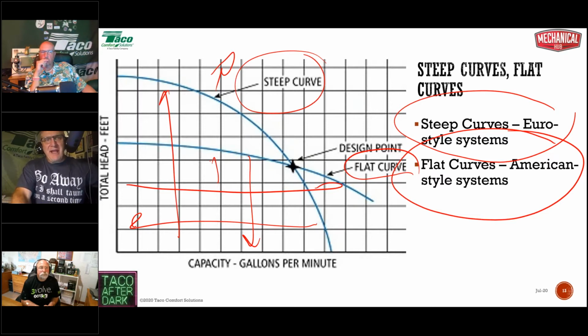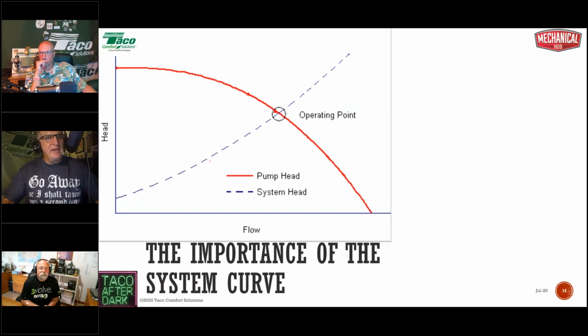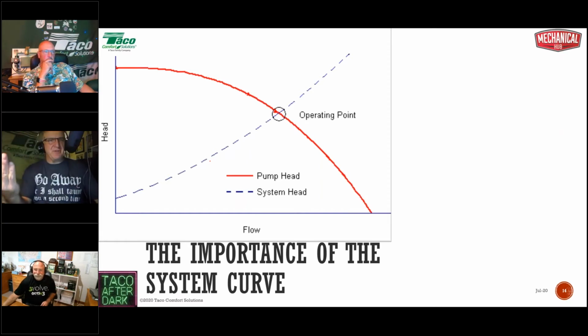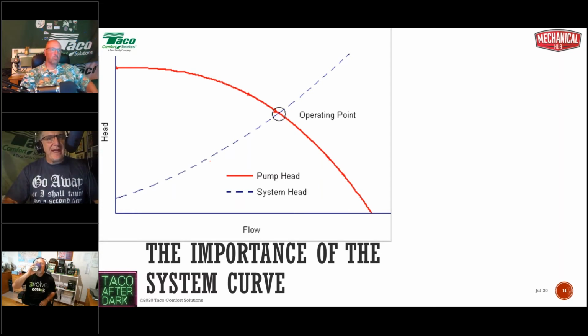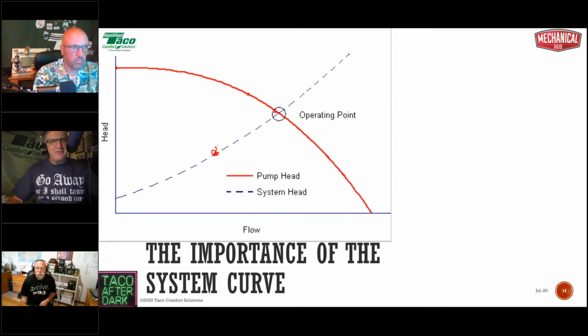The thing that interacts between both of these are system curves, okay? System curves are important. Every circuit of piping and every system has its own unique system curve. We go through a lot of math, and we did it last week and the week before, a lot of rigmarole to find the flow and the head loss through a piping circuit, through a zone. We do an awful lot of work to figure that out. What that really is, it's one point on the system curve plot. I don't know if you guys remember back to 5th grade. You remember doing charts and graphs and doing these little math formulas to come out with different points on the x-axis and the y-axis, putting them together where they intersect, and then doing a bunch of math, putting all these things on a chart and then connecting the dots and seeing what you got.